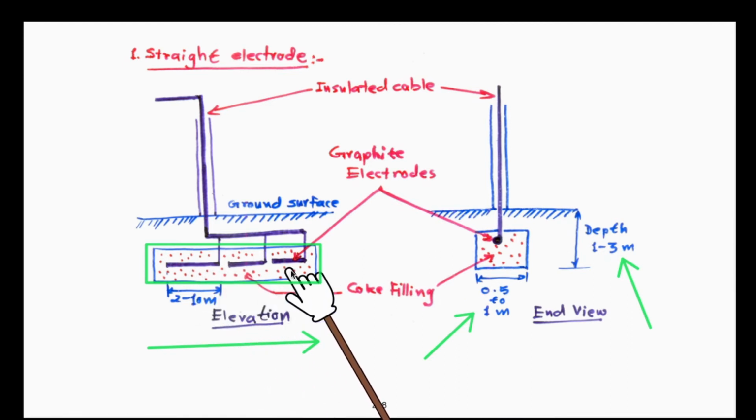So even if there are 3, which are placed at a certain distance, what will happen is that you may consider if it is 10 meters, then this naturally will be 30 meters. 30 meters is 100 feet, isn't it? It may be straight, all the arrays arranged in series, one after the other, so it will require 100 feet worth of space, and that too, it is dug nearly up to 3 meters below the earth surface and having 0.5 to 1 meter width.